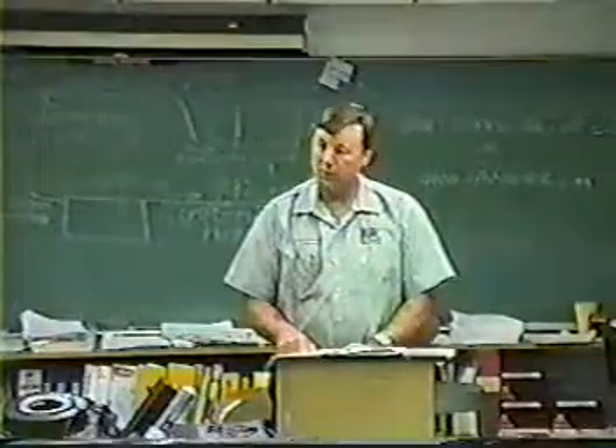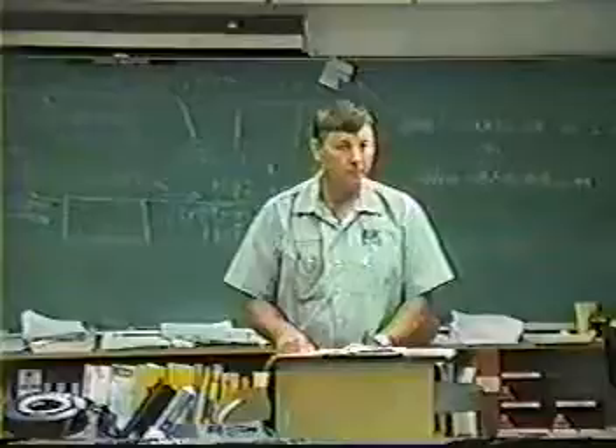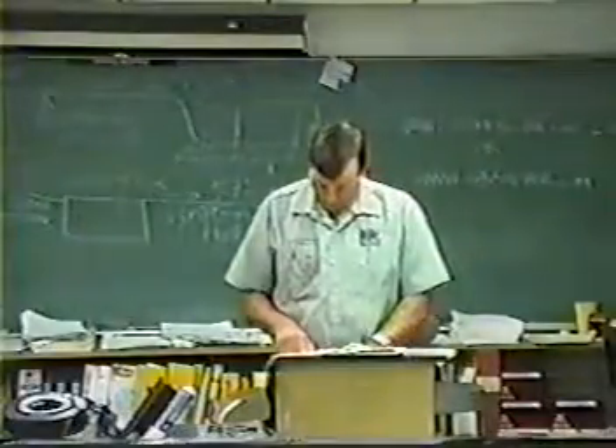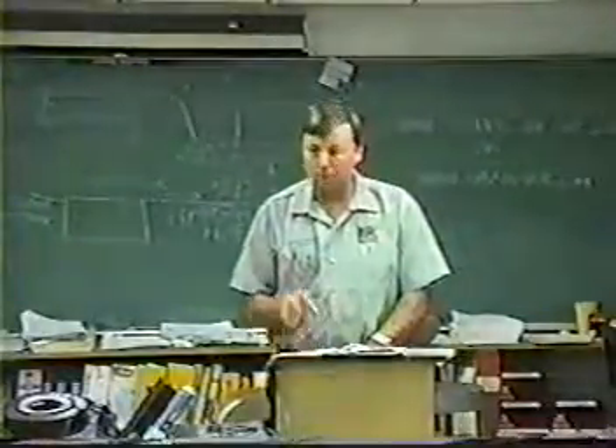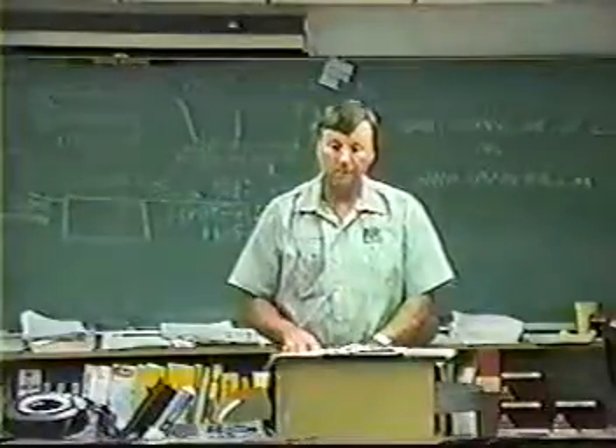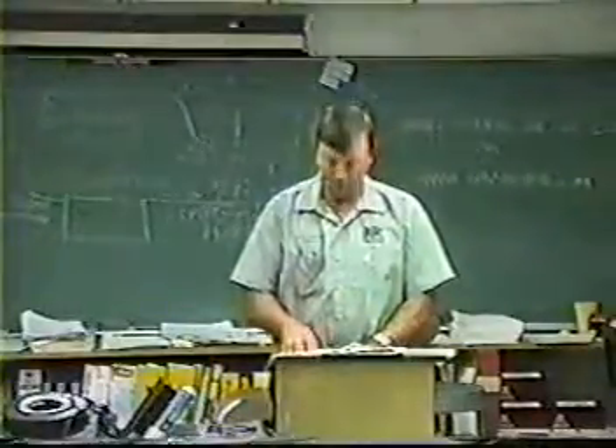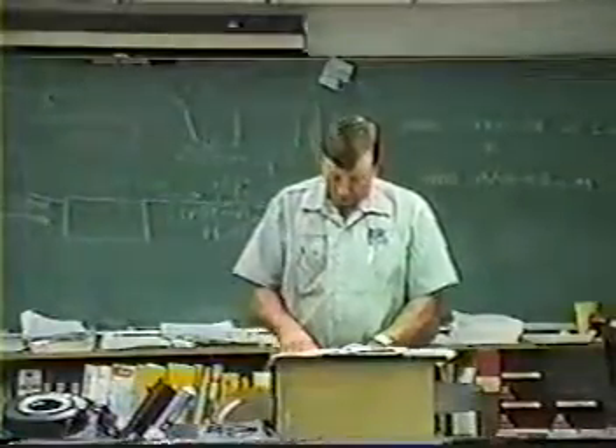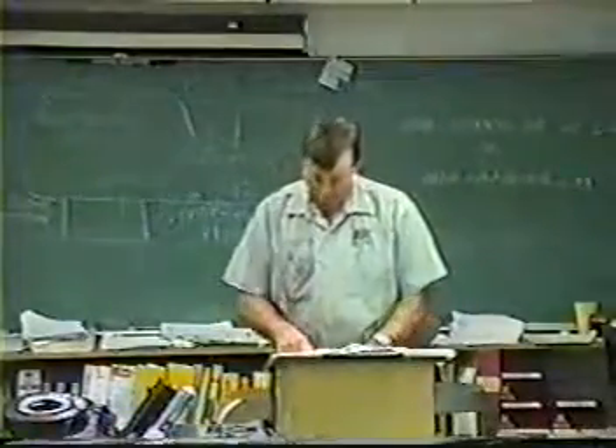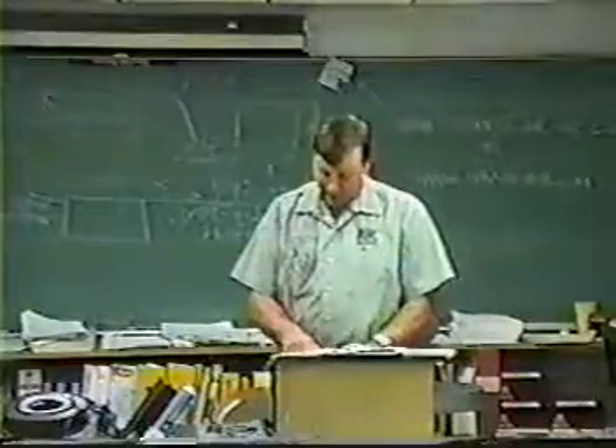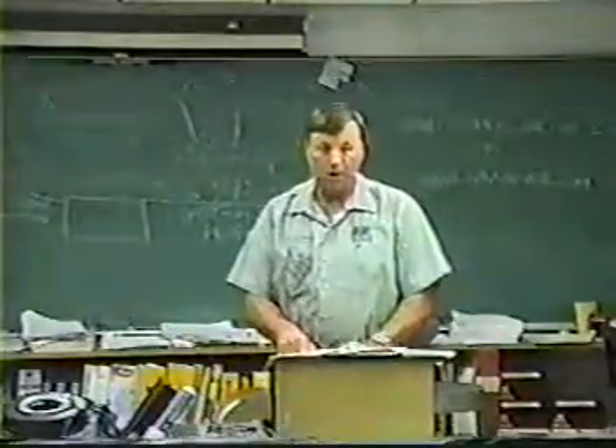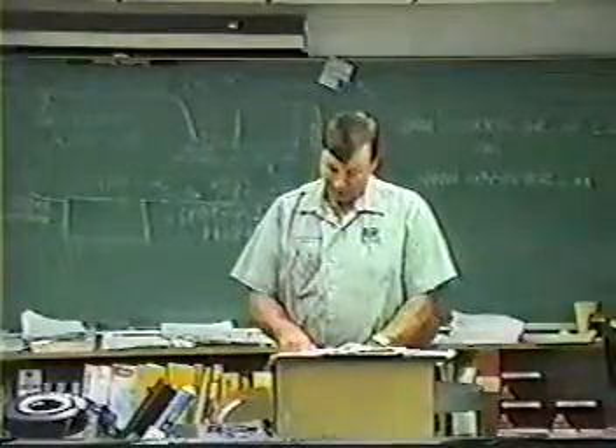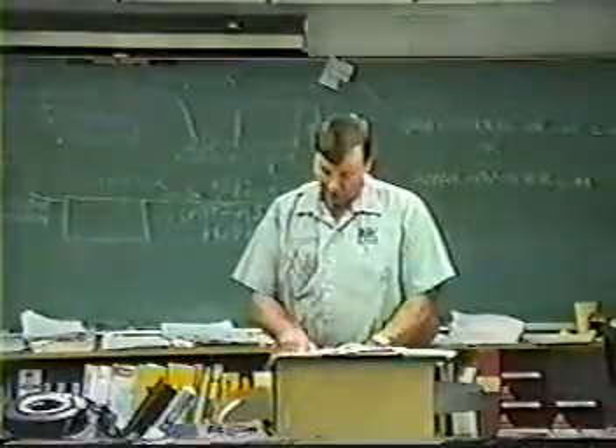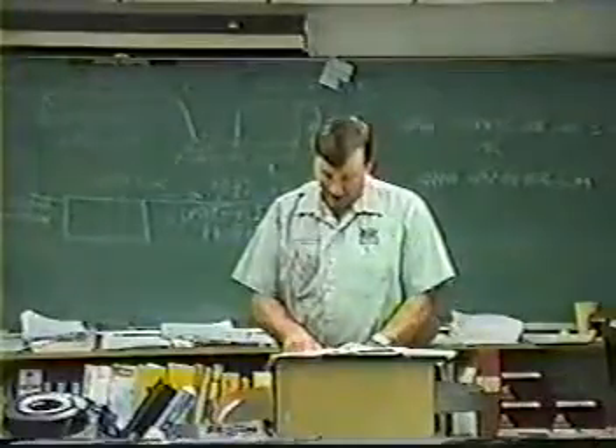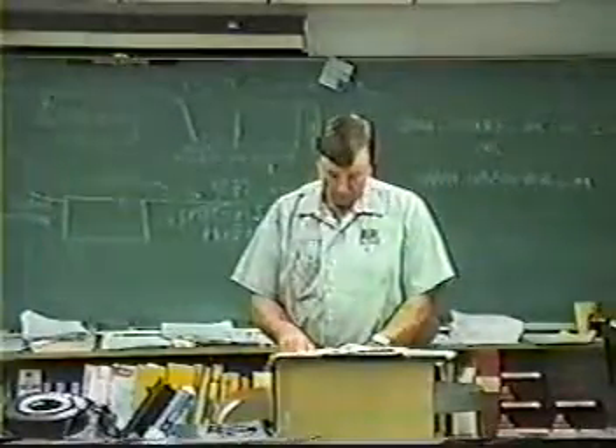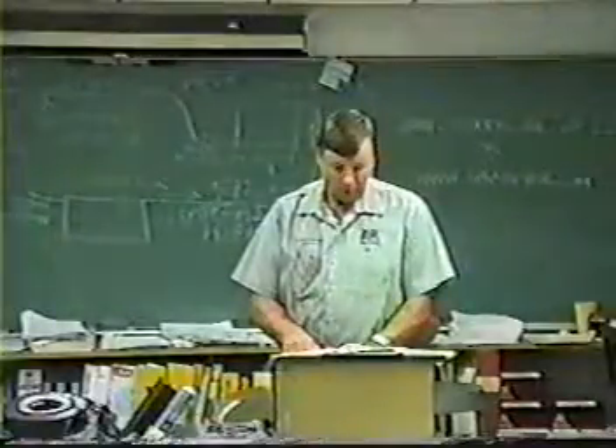That's going to be a test question. Now, see, these are kind of tricky now, so you got to memorize. You're going to see 2 or 3 or 4 questions back to back on this test about these evacuation levels now. So guys, please memorize these. Okay, number 57. The required level of evacuation for recovery equipment manufactured after. Now the key word here is after. November 15, 1993, on a system containing less than 200 pounds of refrigerant is what? 8. Once again, top right corner, right?